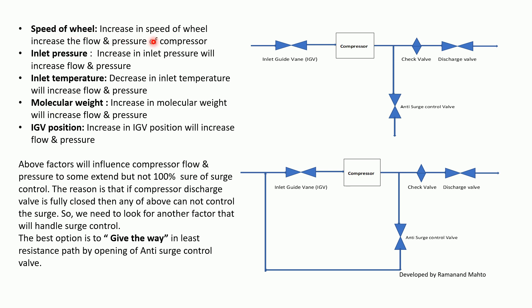Increasing the speed of the wheel increases flow and pressure. Increasing inlet pressure increases flow and pressure. Decreasing inlet temperature increases flow and pressure, and vice versa. Increasing molecular weight increases flow and pressure. Increasing IGV position also increases flow and pressure. Inlet pressure, inlet temperature, and molecular weight are all related to the density of the gas.